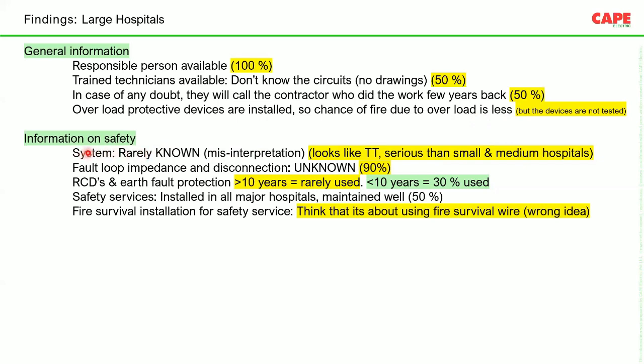With respect to information on safety in large hospitals, the system earthing, like TN-S, TT, IT, is very rarely known, and most often it is misinterpreted. Again, the system looks like a TT, but in a larger hospital this situation is even more serious than in a small or medium hospital. In a small or medium hospital, of course, the supply is LT, whereas in a larger hospital the system looks like TT, but unfortunately it is a very inefficient TN-S or TN-C-S kind of thing. Fault loop impedance and disconnection are unknown in more than 90% of cases.